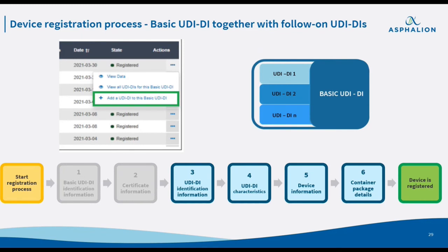Additionally, in case a product family consists of more than one medical device, it is possible to add more UDI codes within the context of a record of a basic UDI of a product family. To do so, select the option that appears on the slide and enter only the information related to the UDI: in this case, the UDI identification information, UDI characteristics, device information, and container package details. Then submit the information, and you will be either in the registered state or in the submitted state mentioned before.